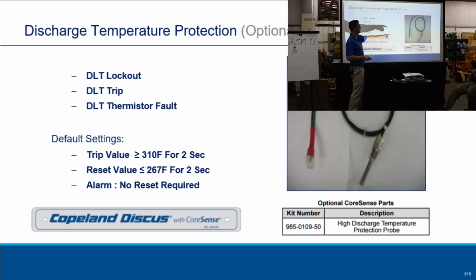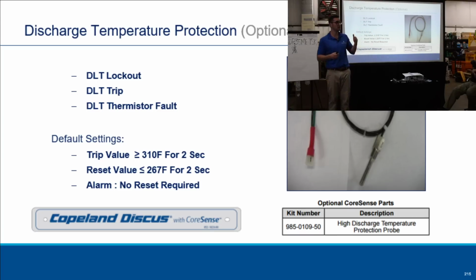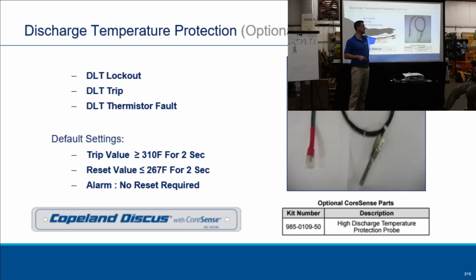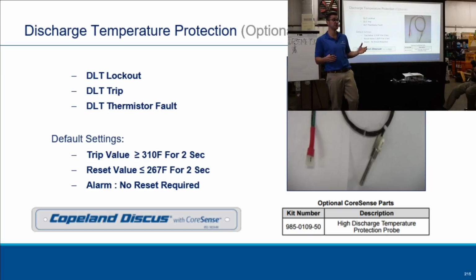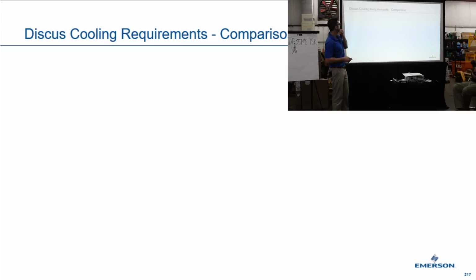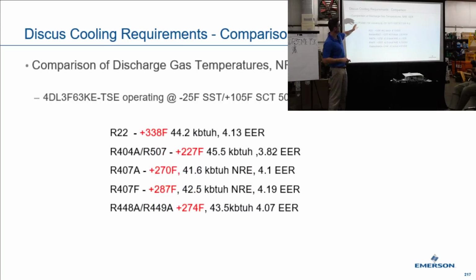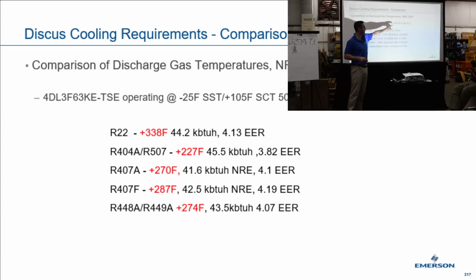But in that CoreSense, you can put a discharge temperature probe. In North America, we don't sell the discharge temperature probe inside the Discus compressors. So what you have to do is talk to your wholesaler and say, listen, I've got a bunch of CoreSense on my semi-hermetics, I want to protect my customer's equipment more for a less expensive probe. That's definitely less expensive than replacing a compressor. You could buy a ton of these and put them in all the compressors in the whole facility. So look into that. Additional cooling methods are super important. Discus cooling requirements, just to show you: this compressor at minus 25, a 4D, minus 25, 105, 50 return gas, R22, 338.